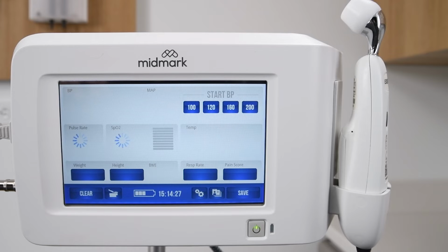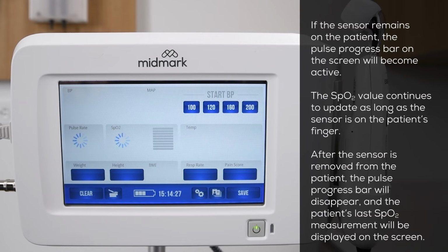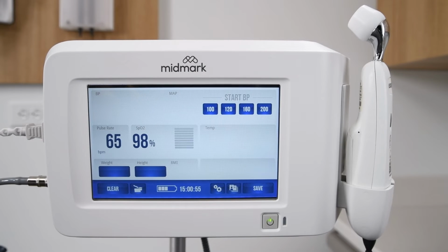When the SpO2 measurement is complete, an audible tone will sound and the SpO2 value will appear. The SpO2 value continues to update as long as the sensor is on the patient's finger. Should a measurement time exceed 10 minutes for one patient, error code 312 will be displayed alerting the user that the SpO2 measurement has exceeded the 10-minute time limit.